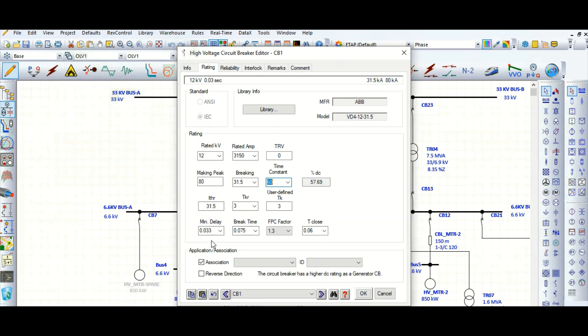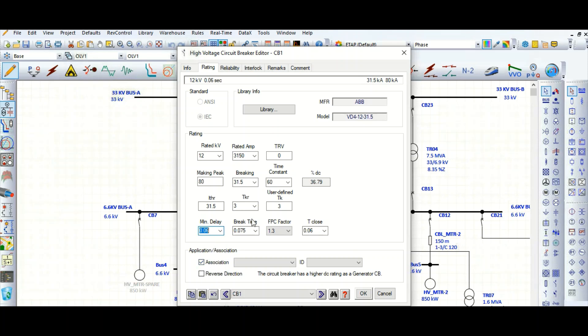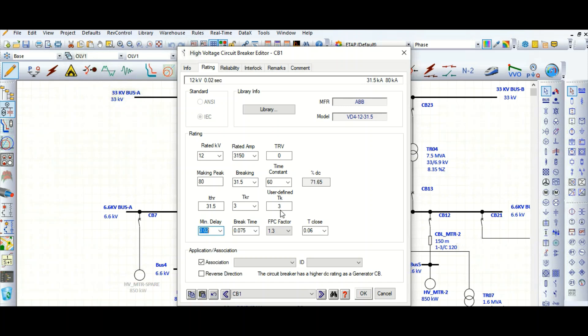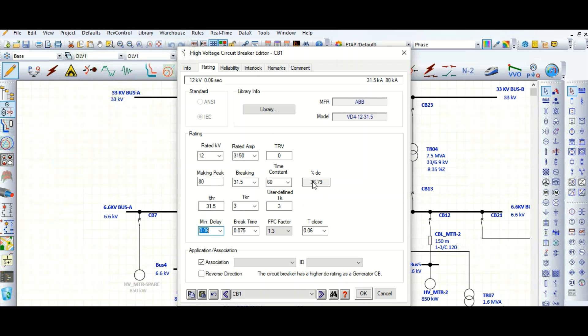You can also define user-defined values in seconds. Here is the minimum delay — suppose you want to close the circuit breaker after 60 milliseconds, you can set that here and see the percentage DC value changing accordingly. At 20 milliseconds, the percentage DC value is higher at 71.65%; as you increase the delay, the percentage DC component decreases.